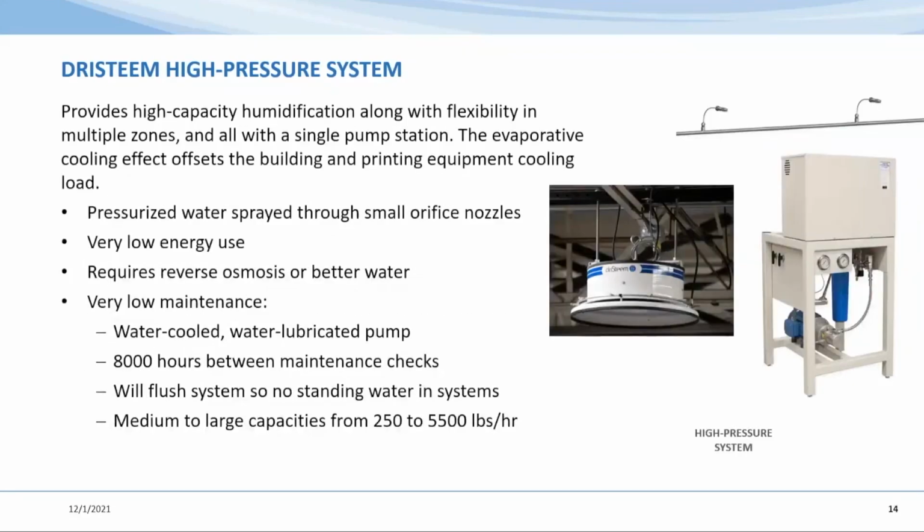DriSteem's high pressure systems are in that adiabatic category, something that we've seen frequently in this space because of that printer technology and it giving off heat regardless of the geographic location. But with this, we can control multiple zones with a single pump station, allowing for a relationship of dispersion to generator or pump that is a greater ratio than isothermal systems, which are 1:1.